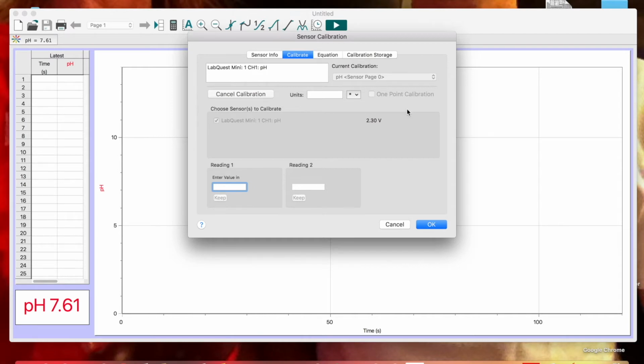So a pH of 4 is a relatively low pH, which means we have a very high, relatively speaking, H+ concentration. So we expect a larger difference between the H+ concentrations inside and outside the probe, which is what this difference in voltage is showing you. So 2.30. Again, I would like this to be stable and not moving around for maybe 10 to 15 seconds, and I haven't seen it move yet since I've been talking. So I think we're good here for the pH of 4 as having that relative voltage.